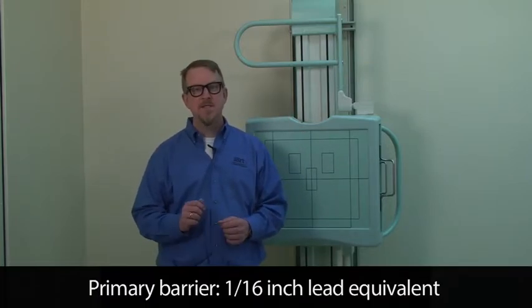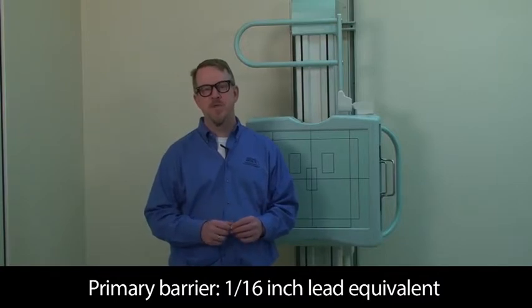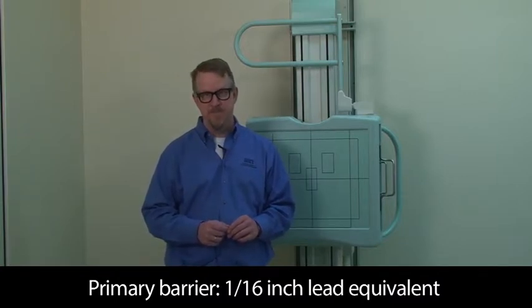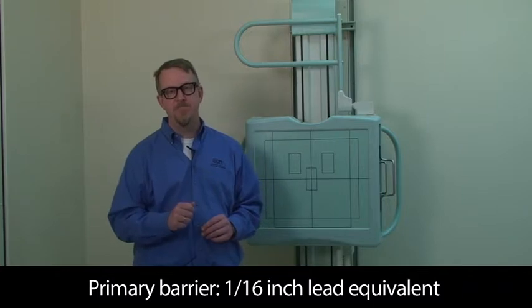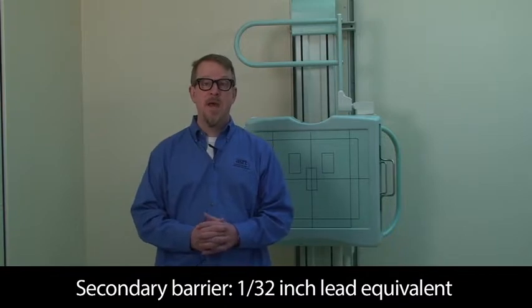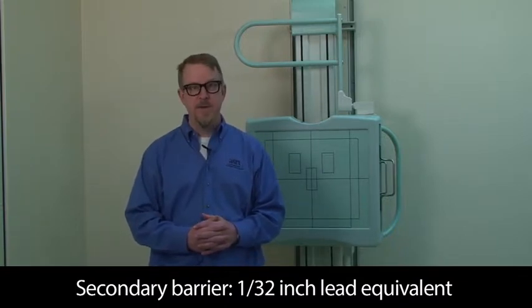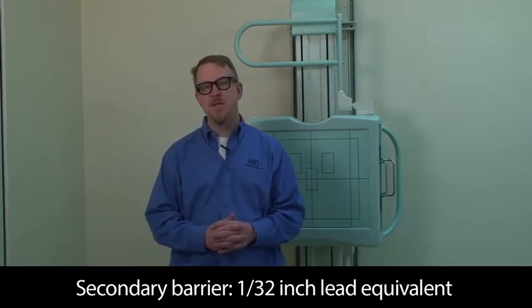Any wall, including ceilings and floors, perpendicular to the path of the X-ray beam must have at least an equivalent filtration of 1/16 inch of lead. This is considered a primary barrier. Secondary barriers are used to protect technologists and other personnel from scattered radiation coming from the tube, the beam, or the patient. Secondary barriers can be half that of a primary barrier or the equivalent of 1/32 inches of lead.